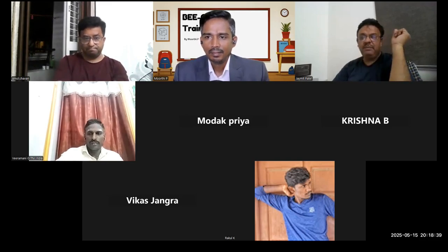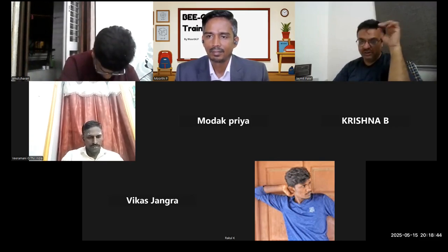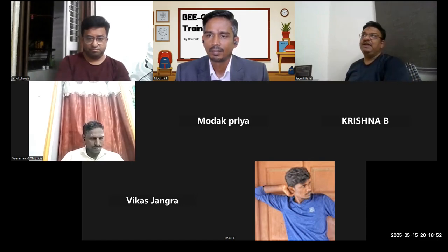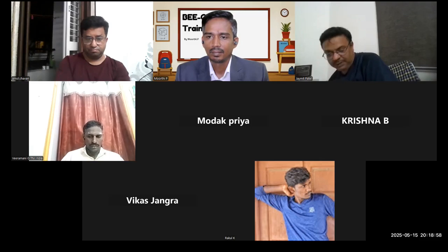After that, we find L5, the loss due to improper combustion: percentage CO into C upon percentage CO plus CO2, multiplied by 5654, divided by GCV of the fuel. This is the improper combustion.